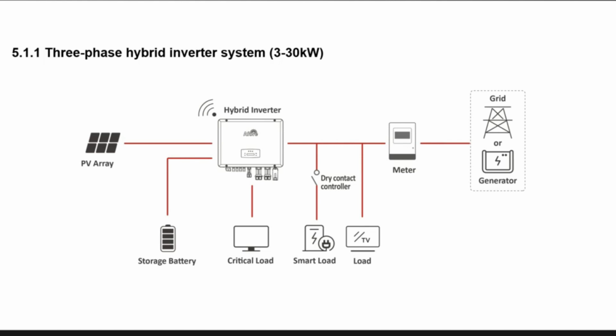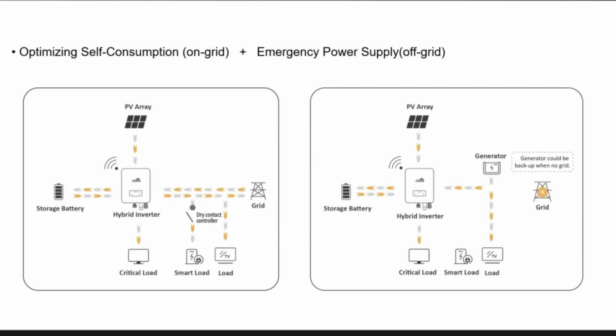This is a typical system wiring of the three-phase hybrid inverter. The same as the single-phase one, with the same function, you can connect a smart load and a generator as a backup. And for the three-phase models, we provide a smart meter as standard. The difference is, for the low power size hybrid three-phase inverter, the smart meter supports the load up to 50 kilowatts. And for the big size, we provide a smart meter which can support a big power load like 500 kilowatts. In that case, it's a meter with 3 CTs together.